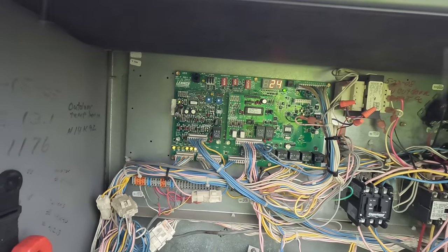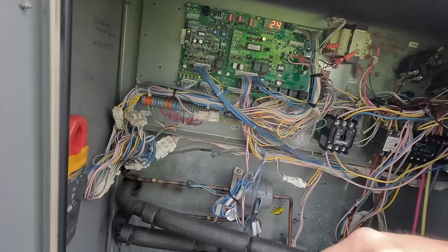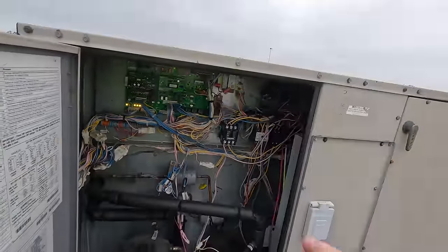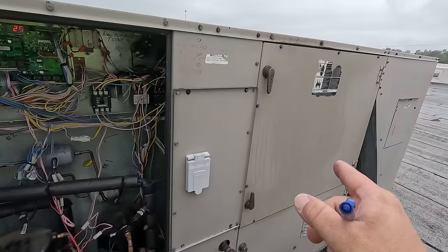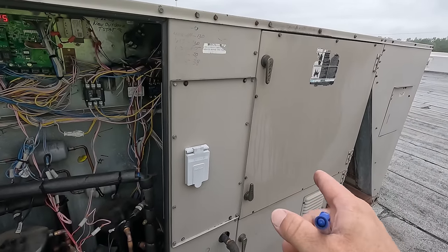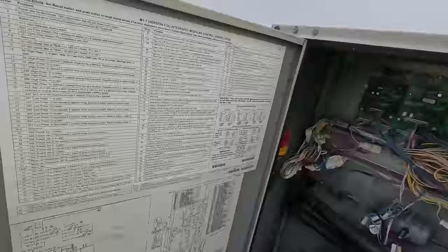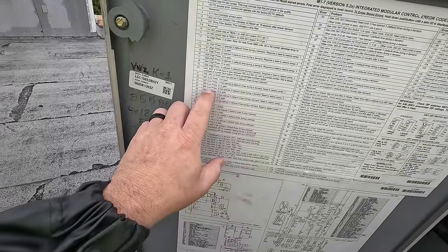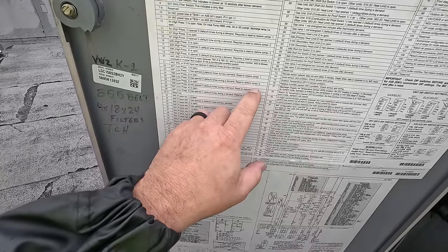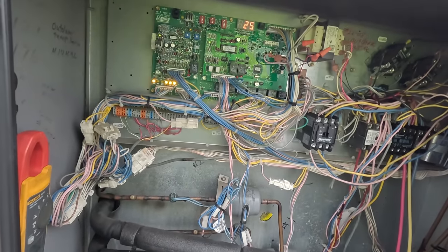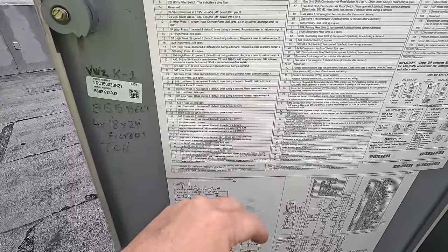Hit it again — error 24: low pressure switch is open. Now think about that. A low pressure switch will cause that to trip. If the fan would stop running — the blower — your suction pressure would start to drop because you have no load going across that evaporator. We may have a fan failing. Error 25: low pressure switch too. So we have 24 and 25. It opened three times during a demand, three steps to restore compressor. Hit it again — back to 24. So during one demand it tripped that many times.